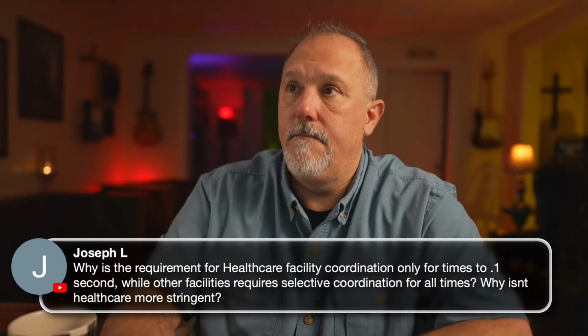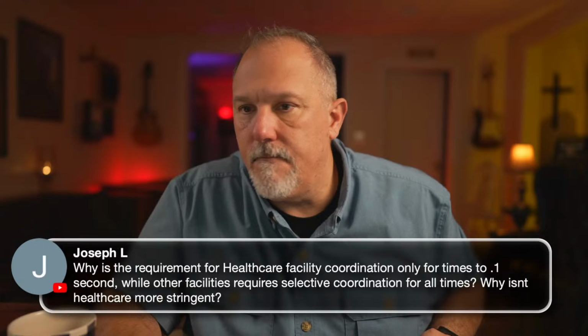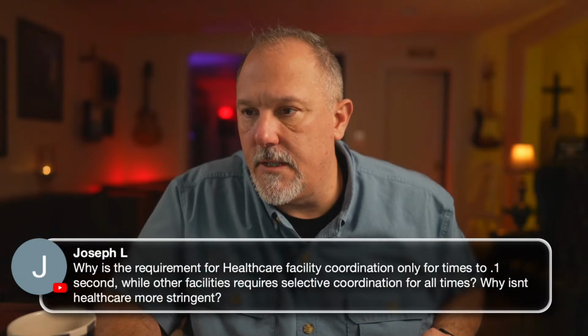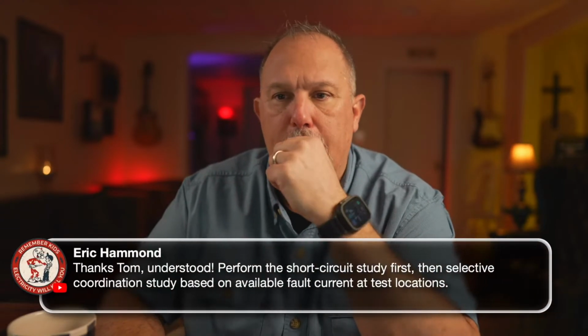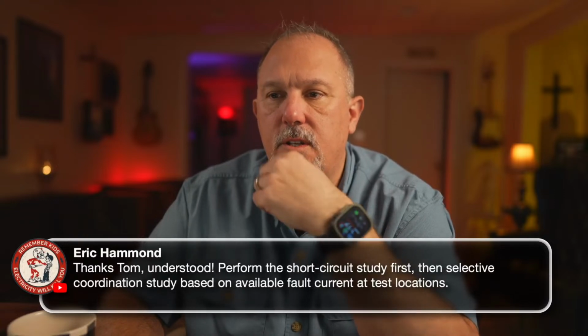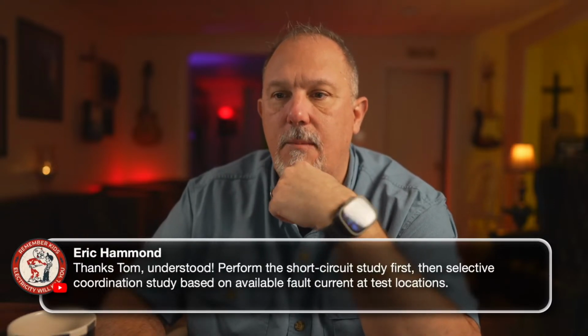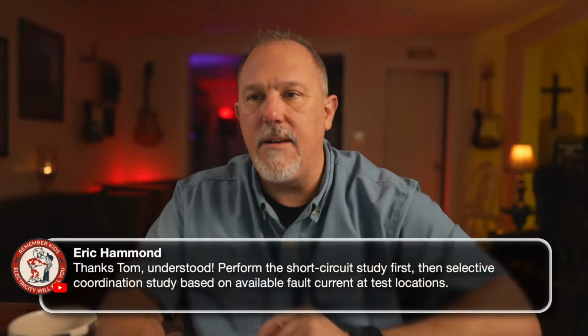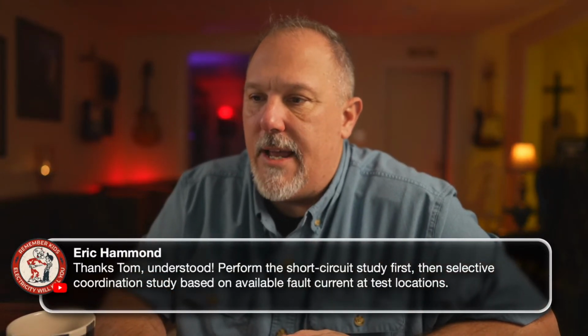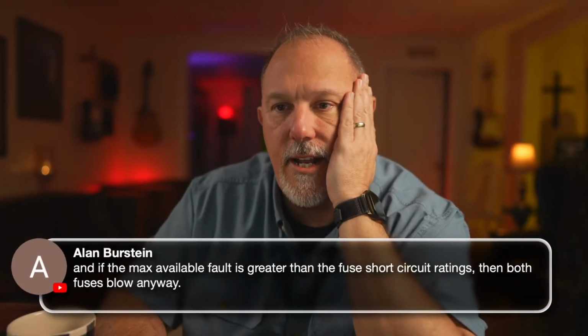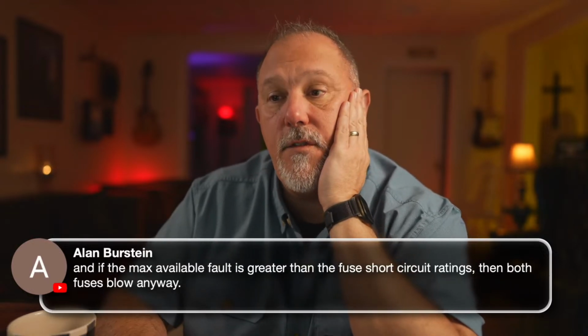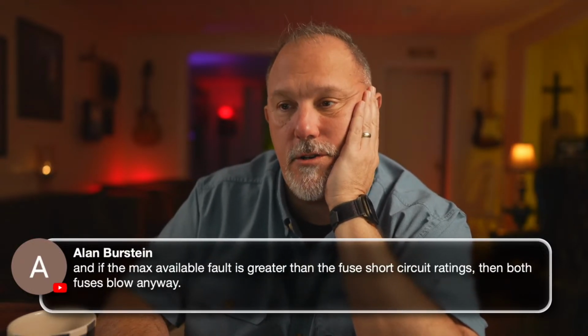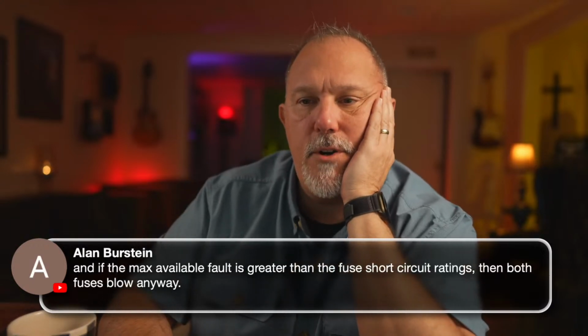All right, let's keep going. Why is the requirement for a healthcare facility? Eric Hammond, thanks, I understood. Perform the short circuit study first, then selective coordination study based on the available fault current. Amen, brother. Alan Burstein: if the maximum available fault current is greater than the fuse short circuit current ratings, then both fuses blow anyway.